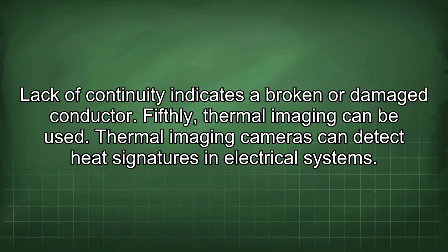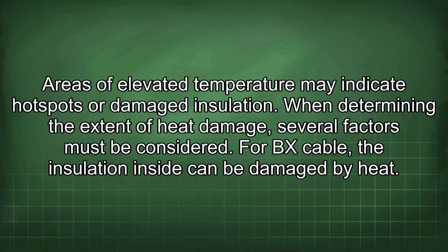Fifthly, thermal imaging can be used. Thermal imaging cameras can detect heat signatures in electrical systems. Areas of elevated temperature may indicate hotspots or damaged insulation.